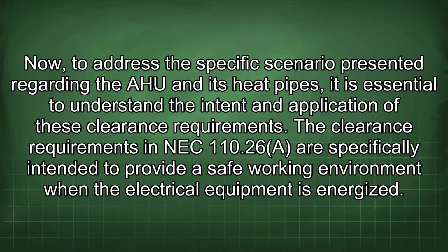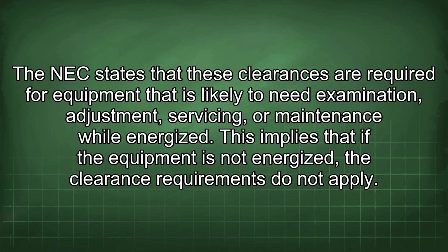Now, to address the specific scenario presented regarding the AHU and its heat pipes, it is essential to understand the intent and application of these clearance requirements. The clearance requirements in NEC 110.26 are specifically intended to provide a safe working environment when the electrical equipment is energized. The NEC states that these clearances are required for equipment that is likely to need examination, adjustment, servicing, or maintenance while energized. This implies that if the equipment is not energized, the clearance requirements do not apply.